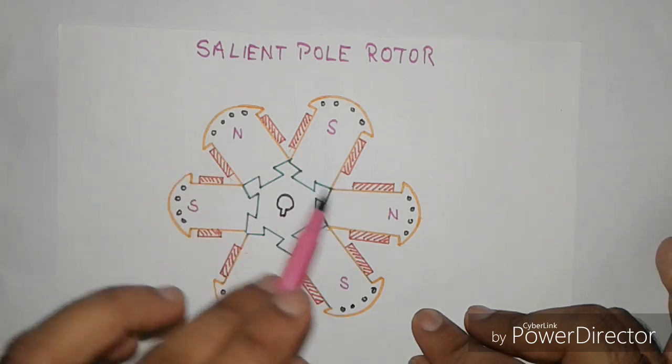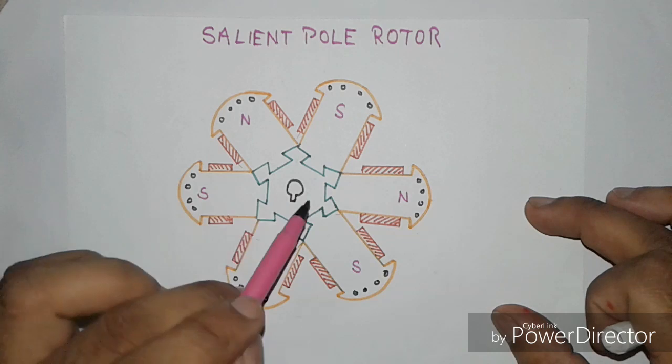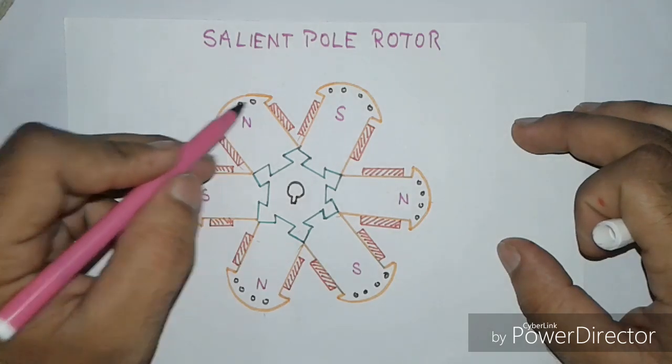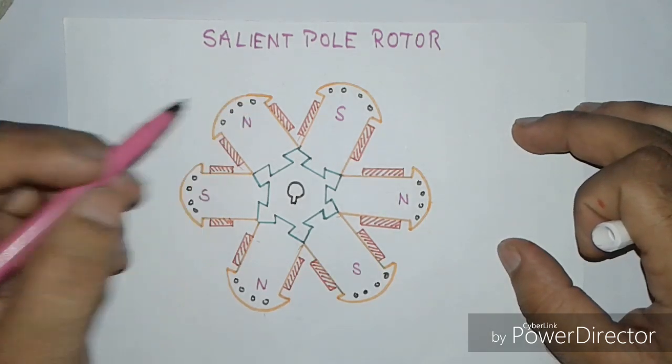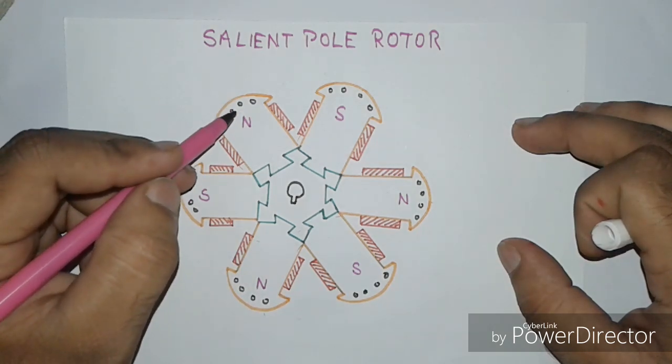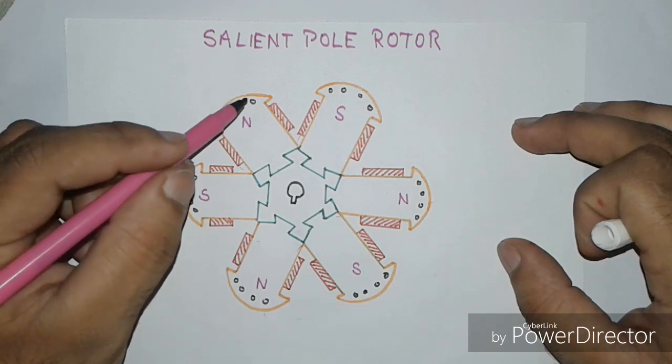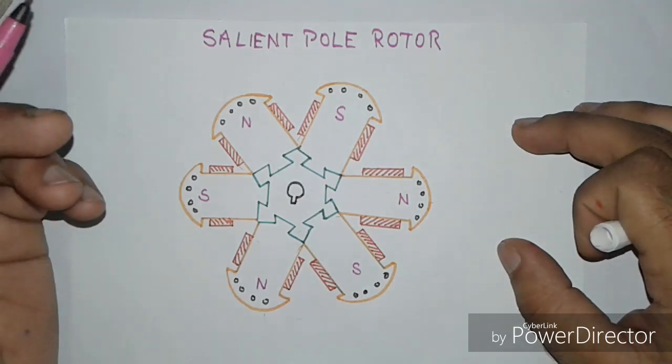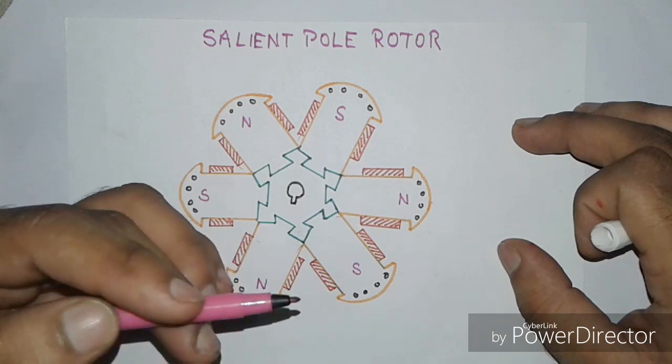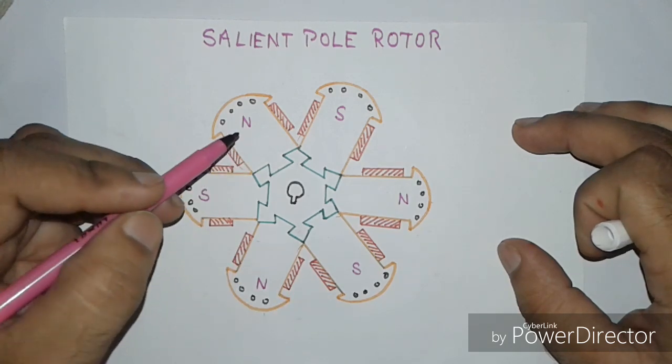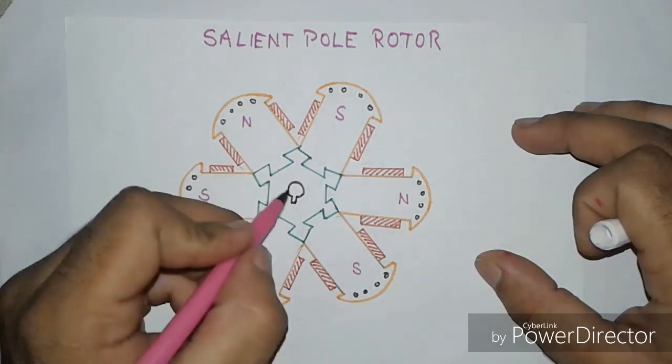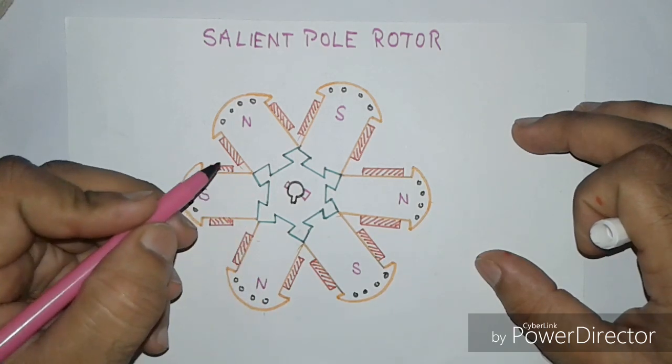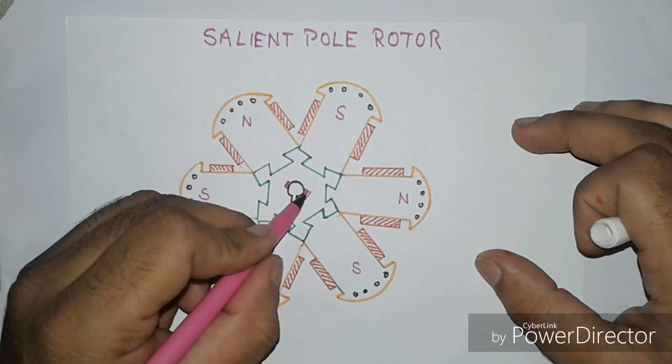The damper winding is made up of copper bars and these bars are usually inserted parallel in the pole face to prevent rotor oscillation during sudden changes in load condition. Both ends of the winding are short circuited and connected to the rings.